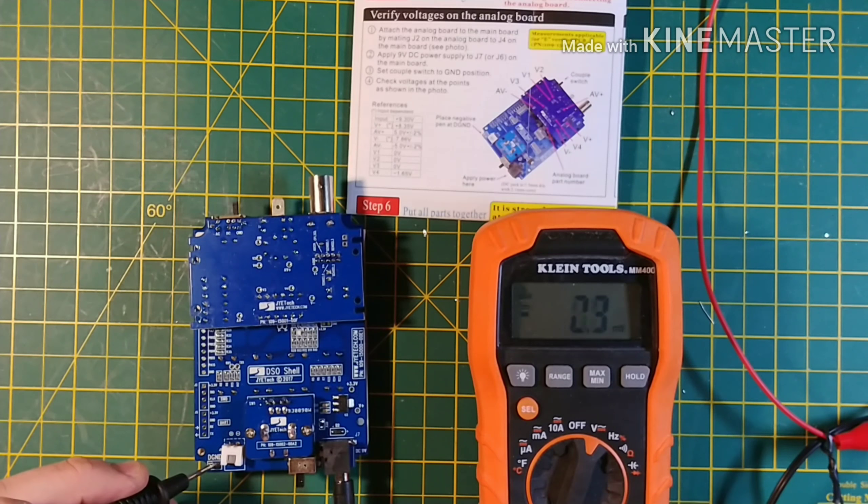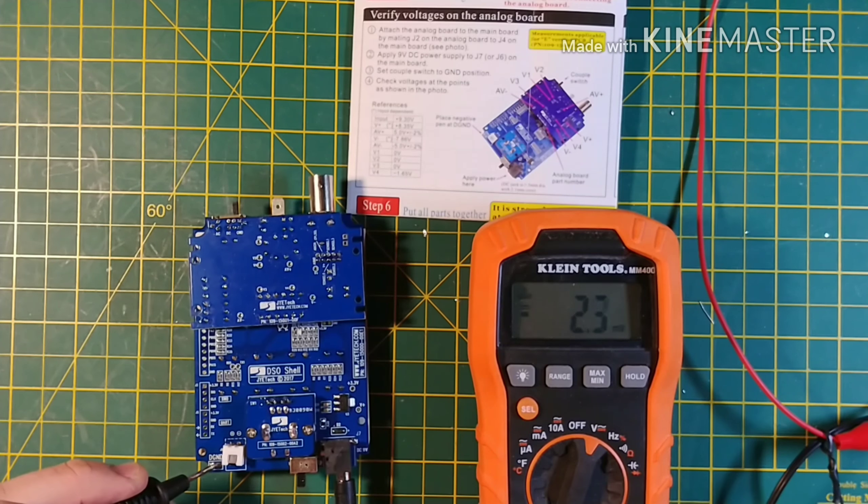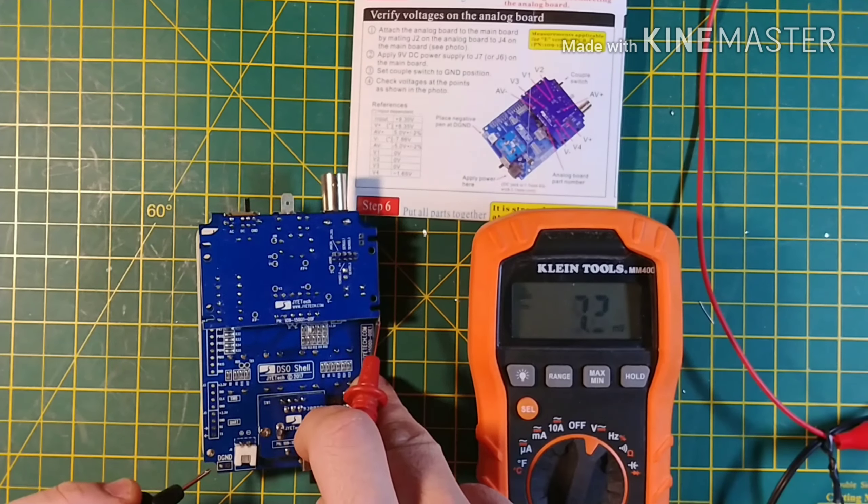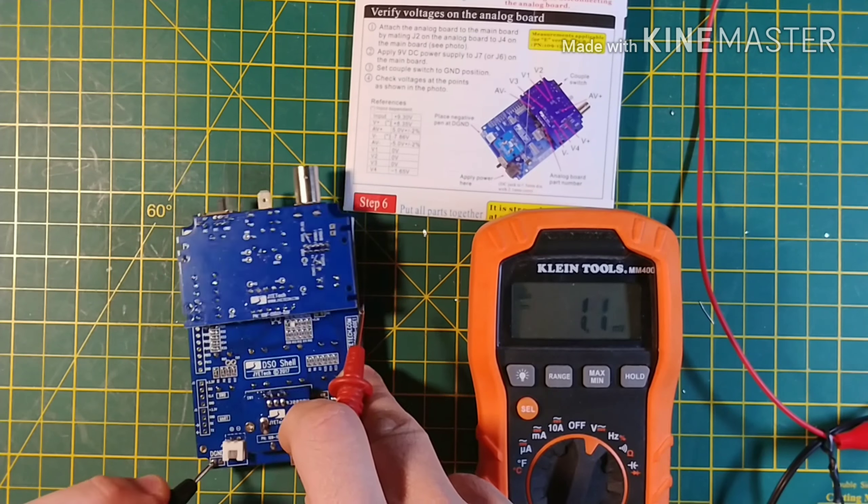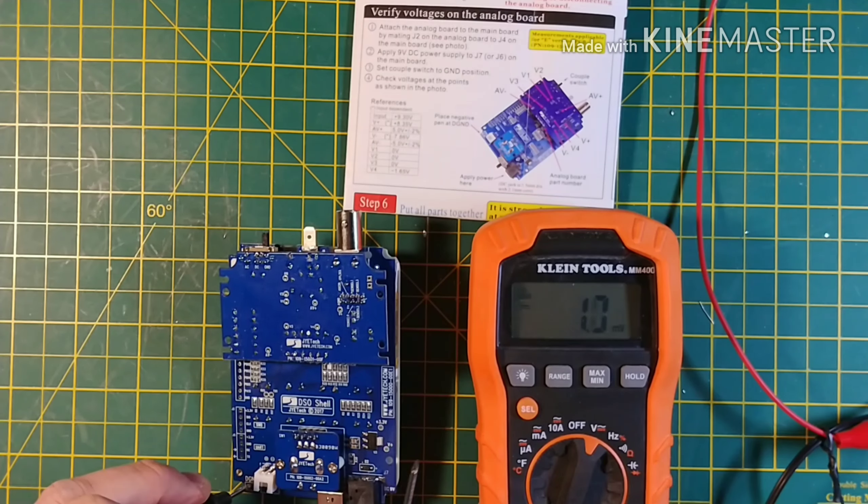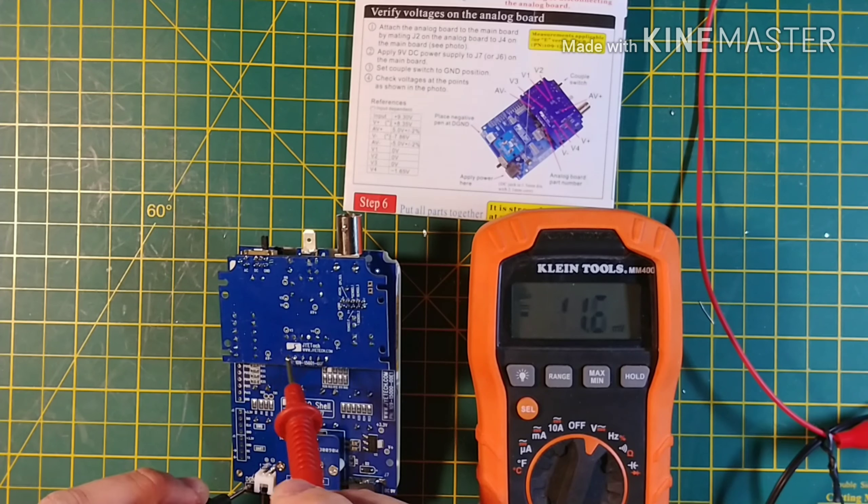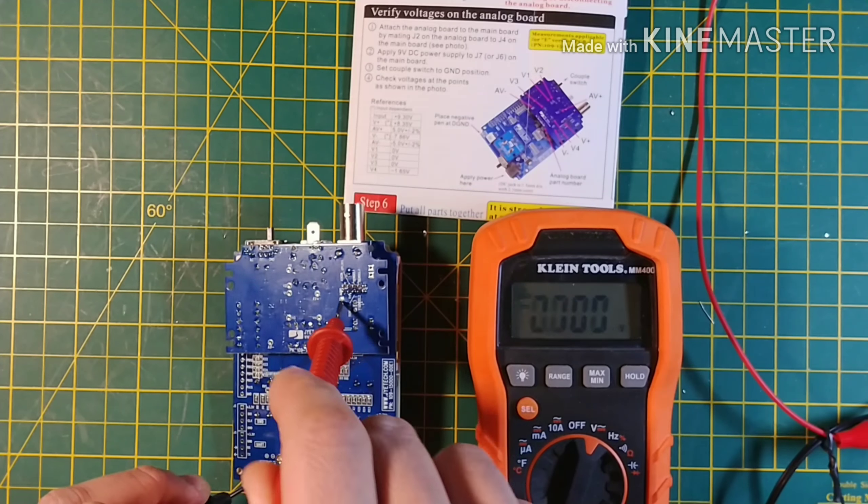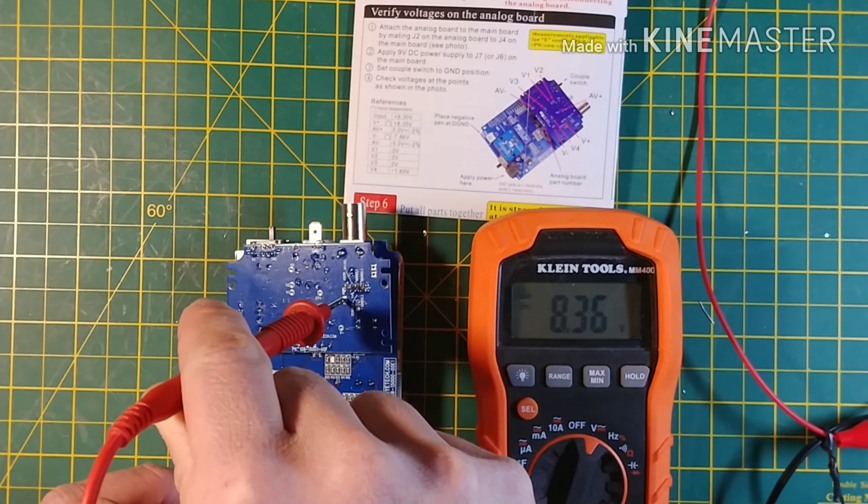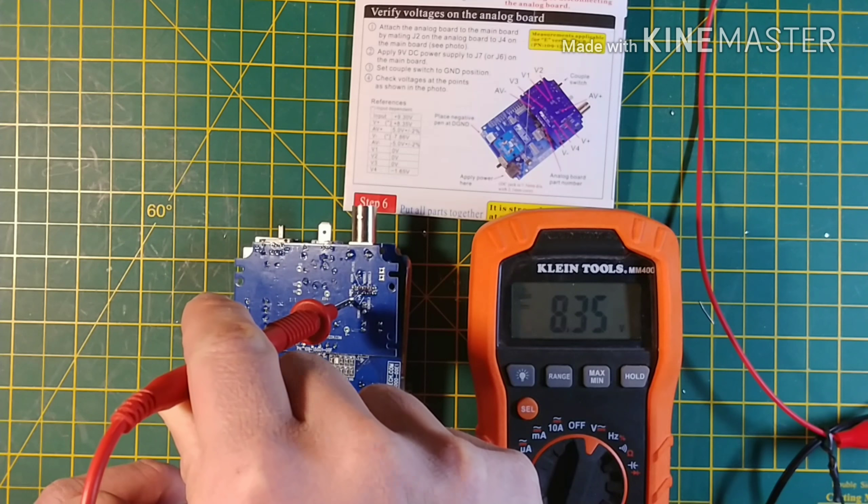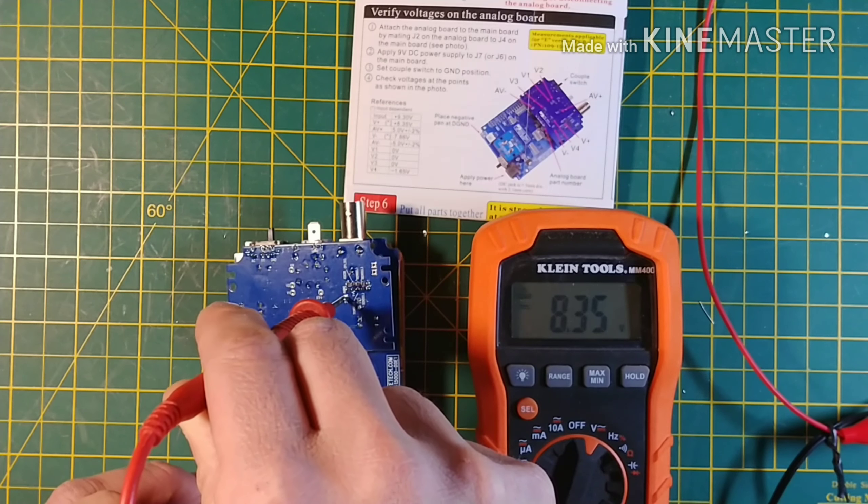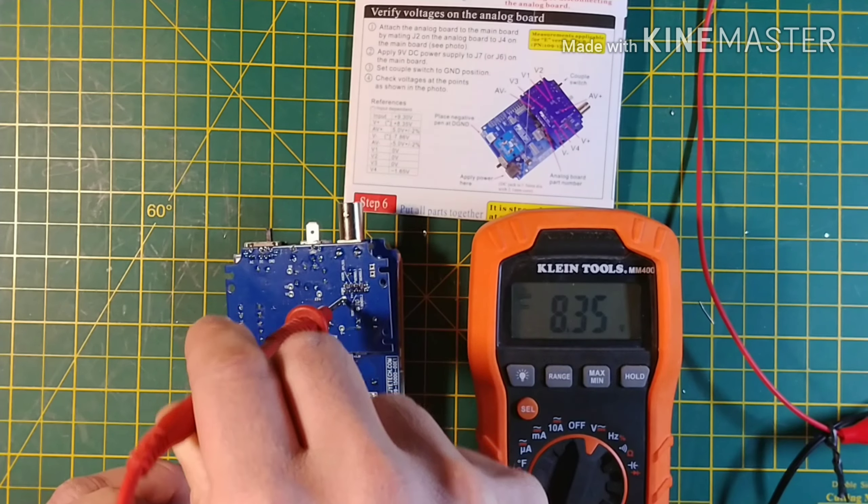Testing from D-ground to the first check pin of V+, which is located right there. Produces a voltage of 8.36. We are supposed to see 8.35. So this is correct.